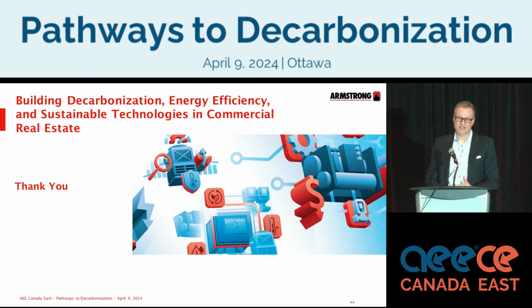this technology is applicable to anywhere where we're moving thermal energy. Heat pumps, heat recovery, incorporating geo exchange, all of it. Because at the end of the day, the way I explain it is all we're doing is we're moving thermal energy from one place to another. And as we move through the pathway of decarbonization, we want to recycle that energy continuously, right? Latent, it's heat of evaporation, heat of solidification, right? So all we're doing now is if I don't need it here, I'm going to move it here. Here's my heating load, here's my cooling load.